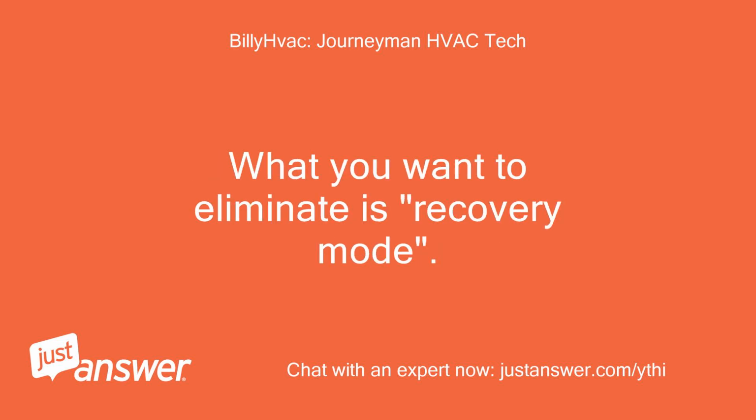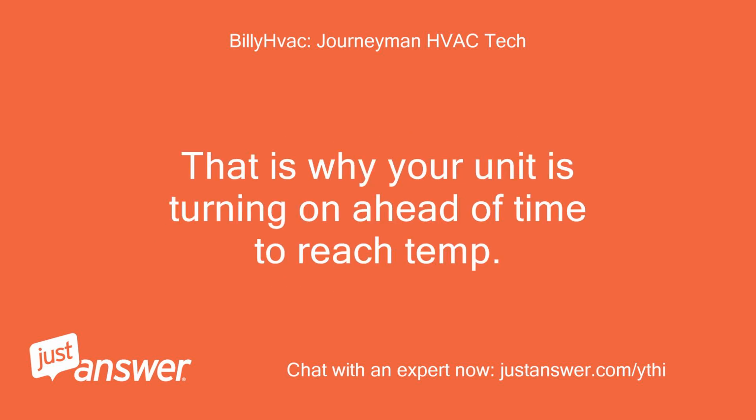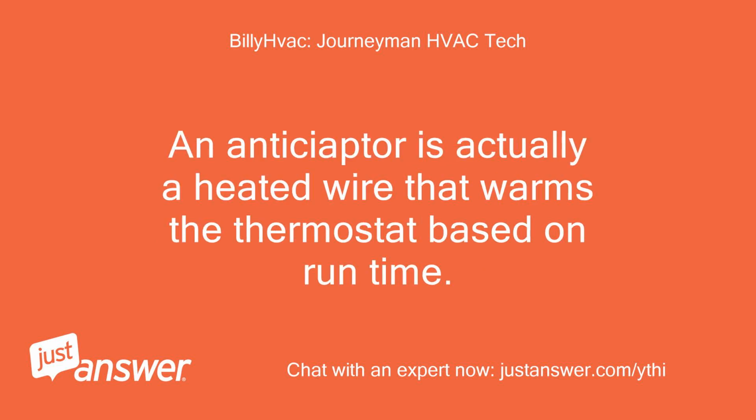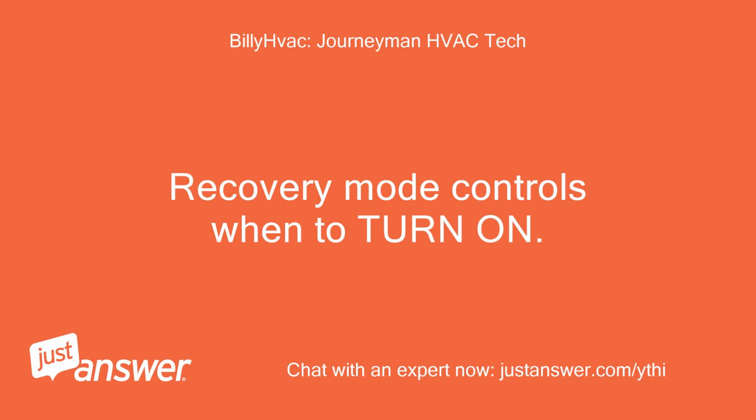What you want to eliminate is recovery mode. This turns on the equipment to slowly reach temp by the time in the program. That is why your unit is turning on ahead of time to reach temp. An ANTICIPATOR is actually a heated wire that warms the thermostat based on runtime. Anticipator controls when to turn off. Recovery mode controls when to turn on.